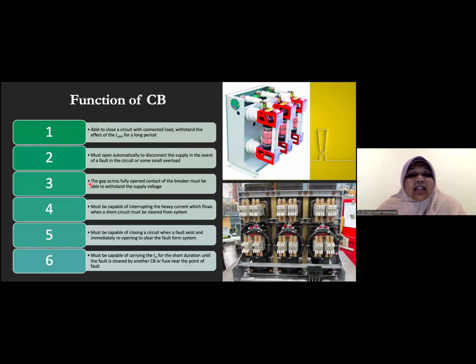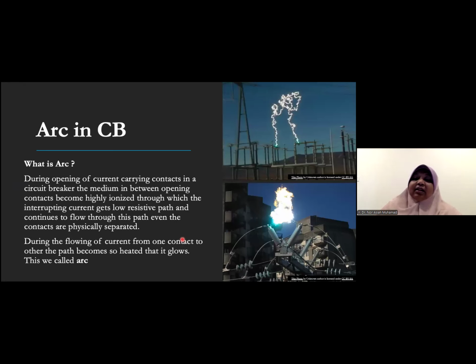So the gap, because it's disconnected, so there are two terminals that need to be separated. And when it's fully open, the circuit should be fully disconnected. So it must be capable of interrupting heavy current, because under operation there is high current. So during interruption, it must be capable of interrupting the short circuit current. They must be capable of closing back or reopening when there are faults. And also must be capable of carrying short circuit current for a short duration during the faults.